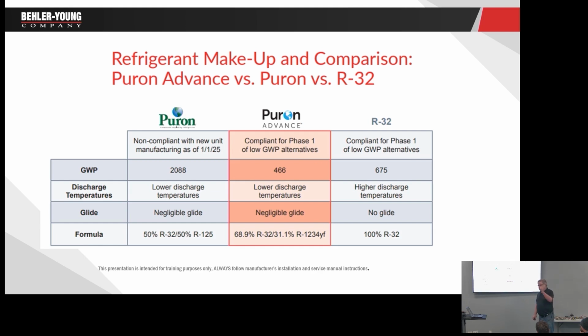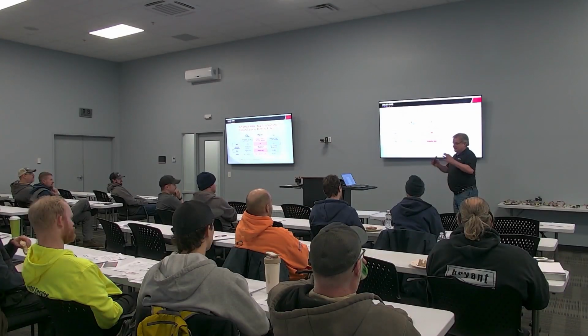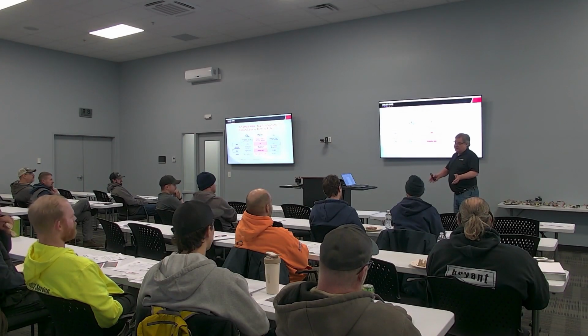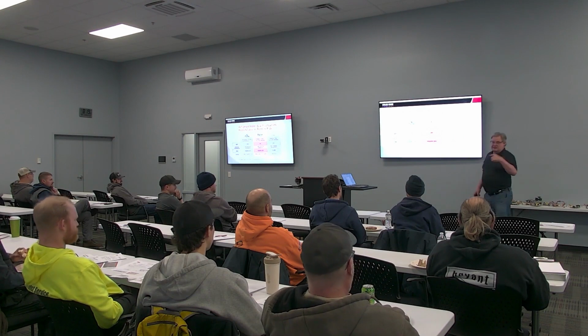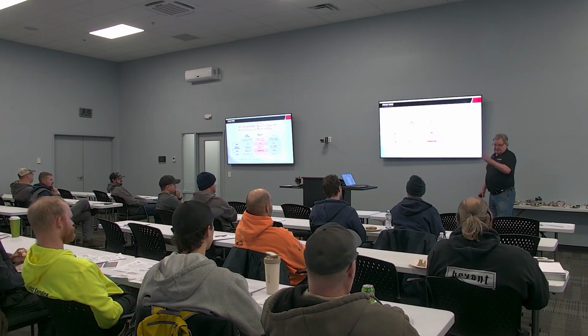Why? Because before you hook up to it, you're going to put an adapter on there. What's the point of that? Because you know when you put that adapter on it, it's a flammable refrigerant. It's not 410. Okay. The tank will also have a red stripe on it. So it'll be really obviously marked that it's an A2L refrigerant.